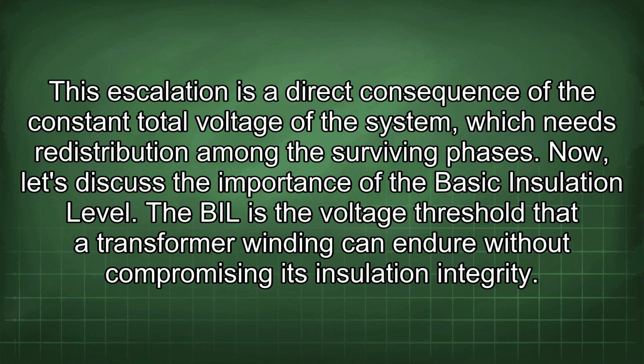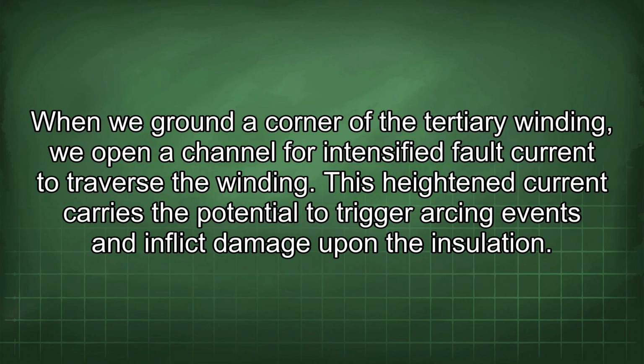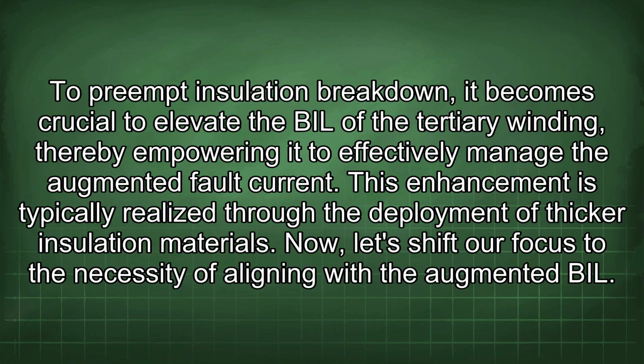The BIL is the voltage threshold that a transformer winding can endure without compromising its insulation integrity. When we ground a corner of the tertiary winding, we open a channel for intensified fault current to traverse the winding. This heightened current carries the potential to trigger arcing events and inflict damage upon the insulation. To preempt insulation breakdown, it becomes crucial to elevate the BIL of the tertiary winding, thereby empowering it to effectively manage the augmented fault current.